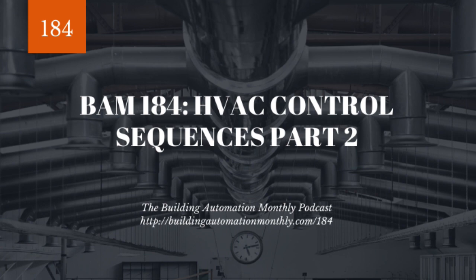This assumes that your outdoor air enable is smart enough to know that, hey, I'm not going to have the outdoor air economizer open when it's 90 degrees. I could see how people could read this wrong and they would be like, oh, my outdoor air damper's open at 90% and both stages are cooling or on, as in the sequence. No, not quite. So it's really important that you understand what is the low point, as well as what is the high point for your economizer enable, because you don't want your economizer open when it's 90 degrees with 60% relative humidity outside and you're just bringing in hot, muggy air that there is no way your building's going to be able to remove with your compressors, and you're just going to destroy your units. You're going to destroy the inside of your building. It's just not good. So I want you to really be aware of that, right?